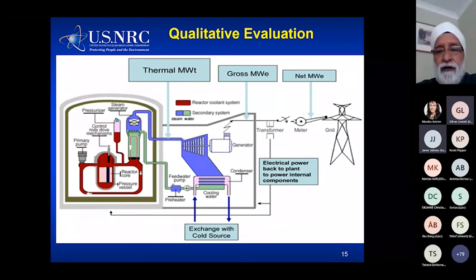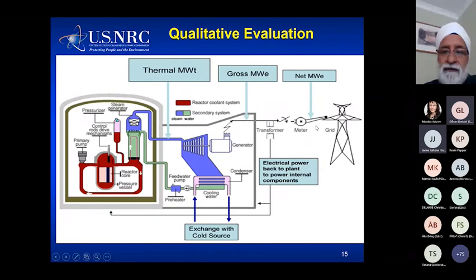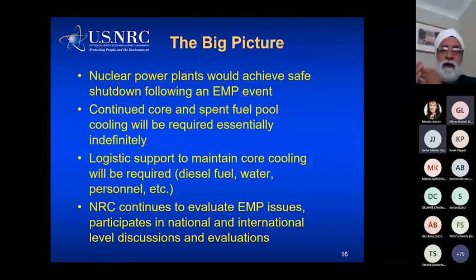Overall, what are we looking at? We're looking at the offsite source, which is the grid, affecting us. We're looking at transformers. We're looking at the impact on the main generator and possibly the cooling water systems. And then inside the reactor vessel, we're looking at instrumentation and control systems that we need to monitor the vessel itself. So what's the big picture? We feel the nuclear power plants would achieve safe shutdown following an EMP event. We feel core cooling capability and spent fuel cooling capability will be required indefinitely, but we feel it'll be there. We would need long-term logistics support for safe shutdown, and we are evaluating other experiences nationally and internationally.